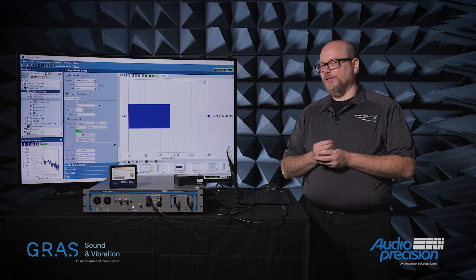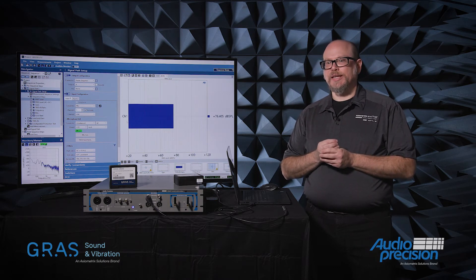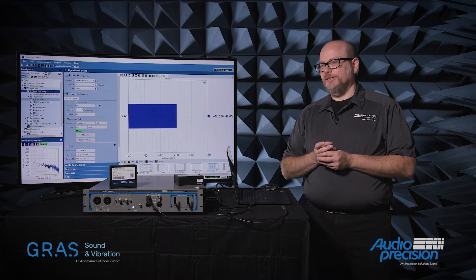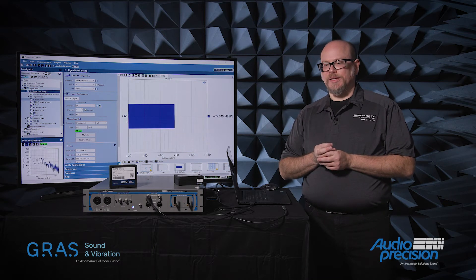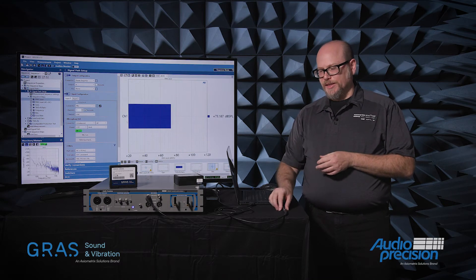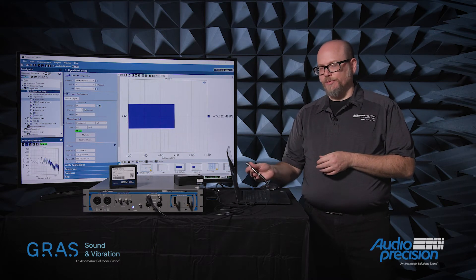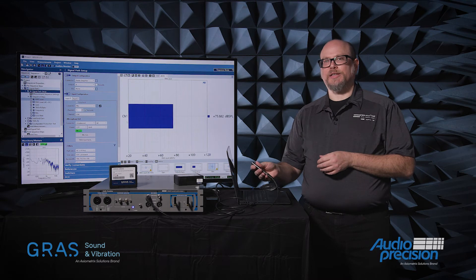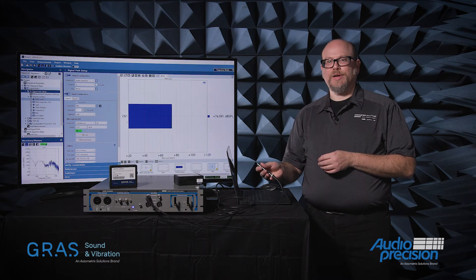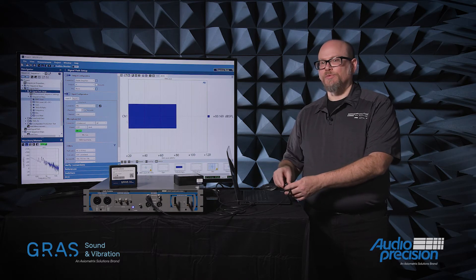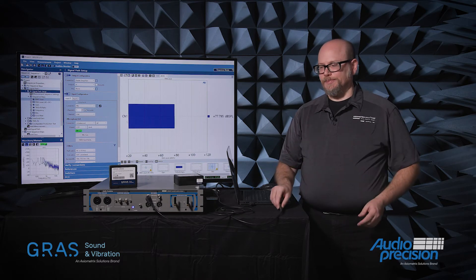The one downside to capturing it via TEDS is that TEDS has not actually measured anything. In this case, the microphone was calibrated at the factory in Denmark. The sensitivity information was programmed into the microphone, and we are simply reading that out.